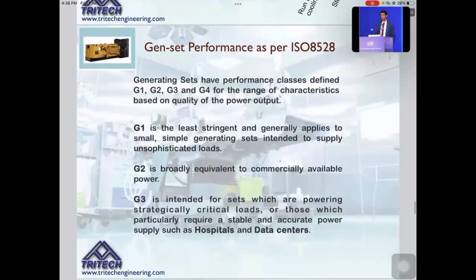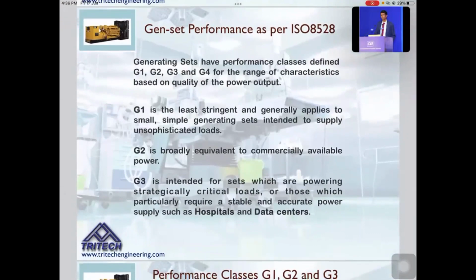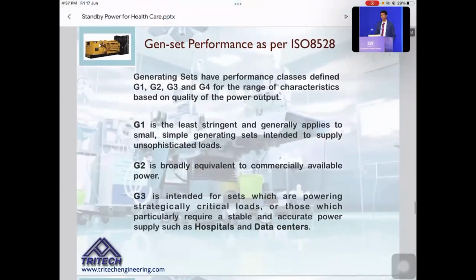Then I just want to highlight a few points on the categorization of the generator sets. There are actually 4 categories of generator, as per the ISO standards. They are called G1, G2, G3, and G4. In the case of a G1 rating, it is for general rated generators, applicable for domestic, residential use. So it is not supposed to be handling sophisticated loads.